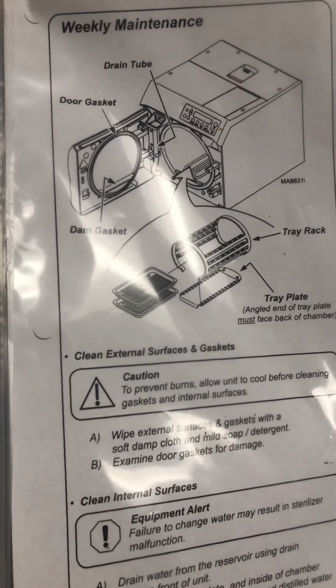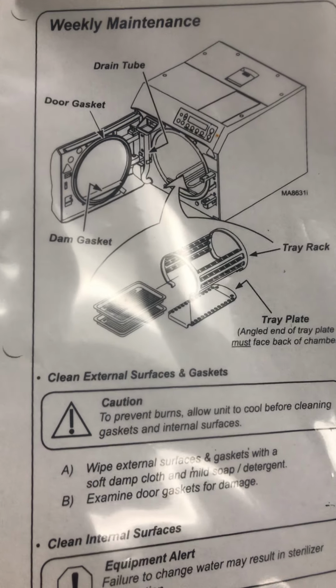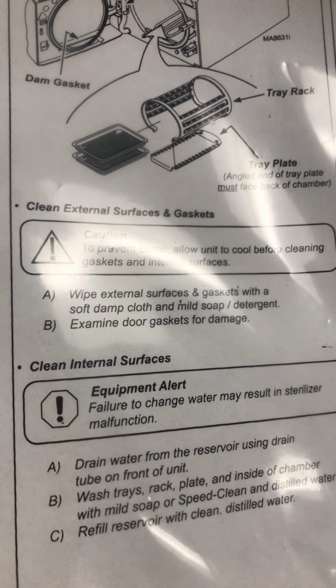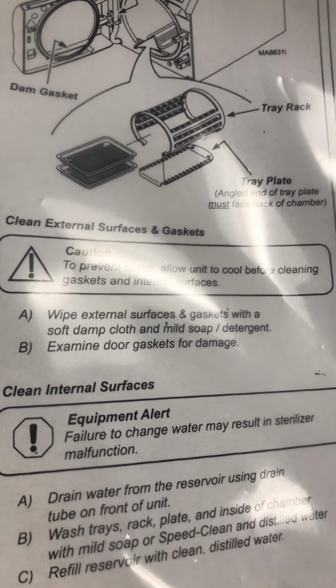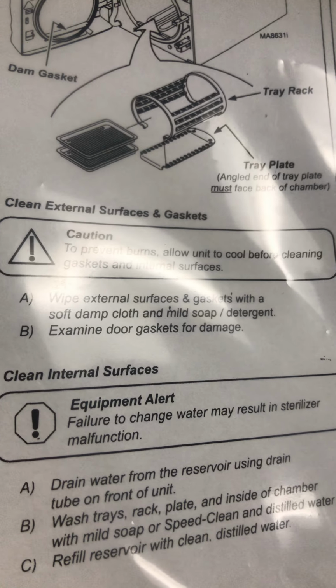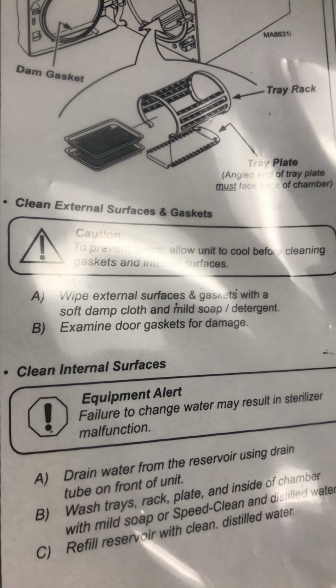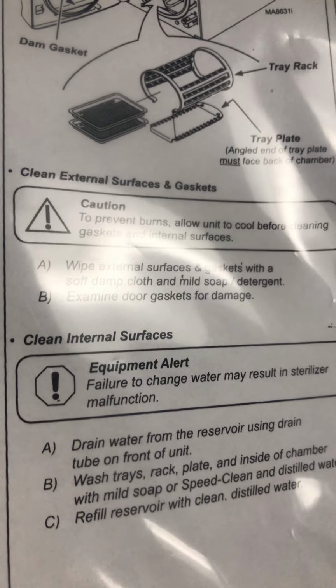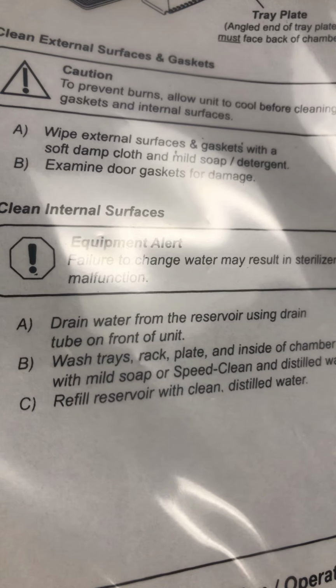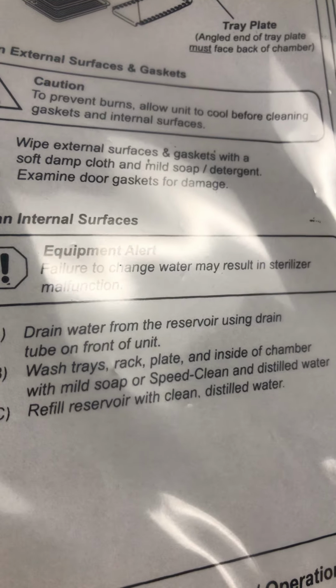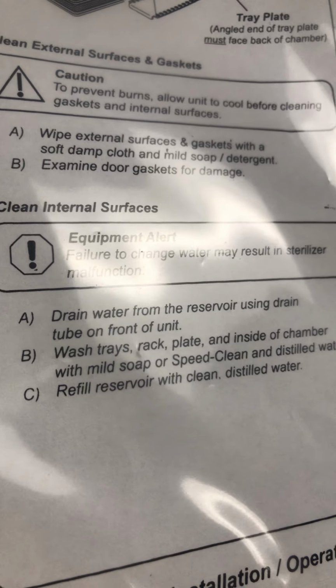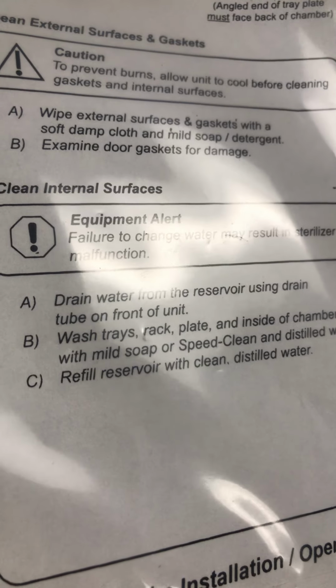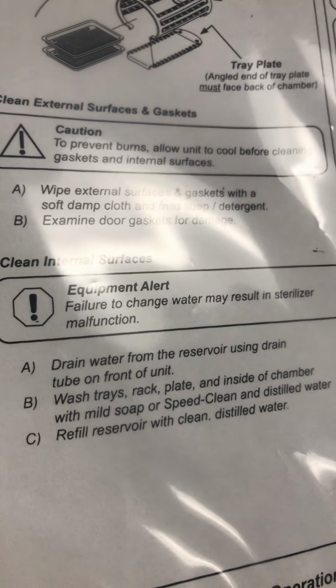And just know too that you have to do weekly maintenance on your autoclave. So the weekly maintenance here, right? You got to wipe it down with a soft damp cloth and mild soap detergent. Look for areas of damage. Drain the water. Wash it out. Refill the reservoir with clean distilled water. Okay, so that's weekly maintenance.